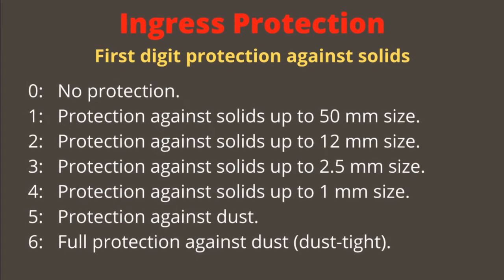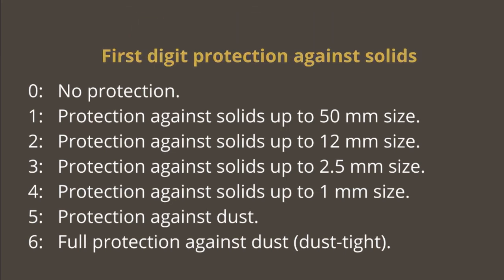The first digit of IP — protection against solids: 0 is no protection; 1 is protection against solids up to 50 mm; 2 is up to 12 mm; 3 is up to 2.5 mm; 4 is up to 1 mm; 5 is protection against dust.